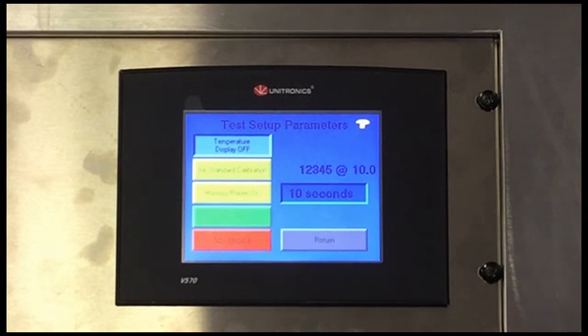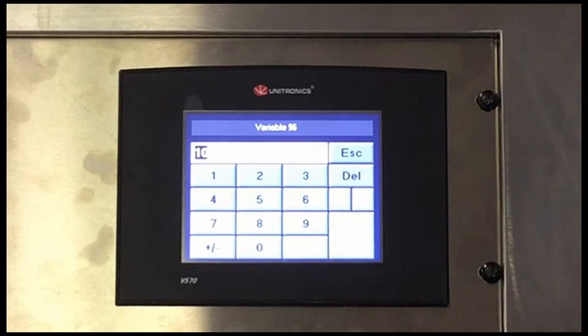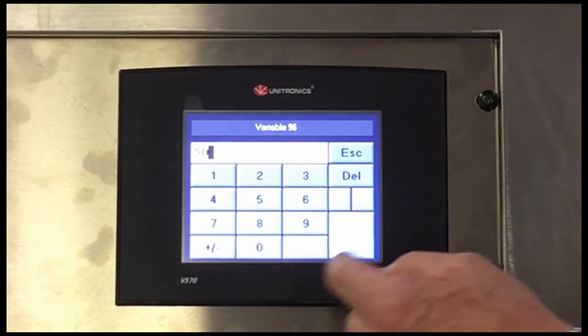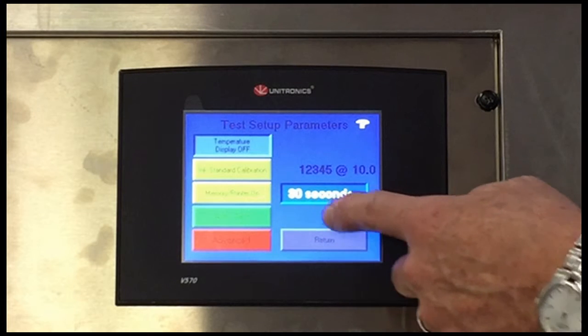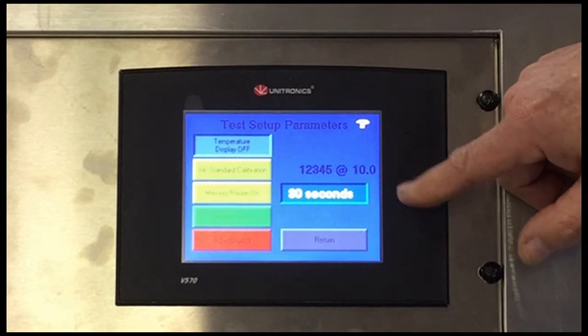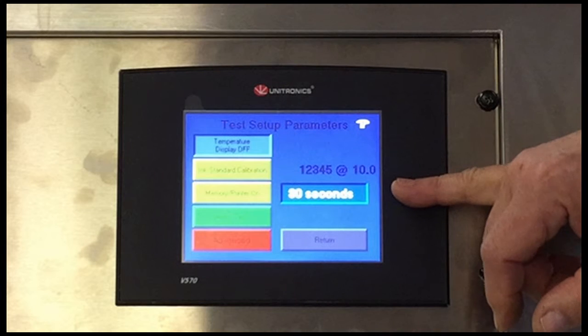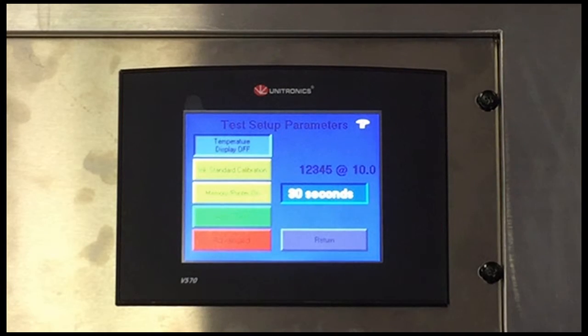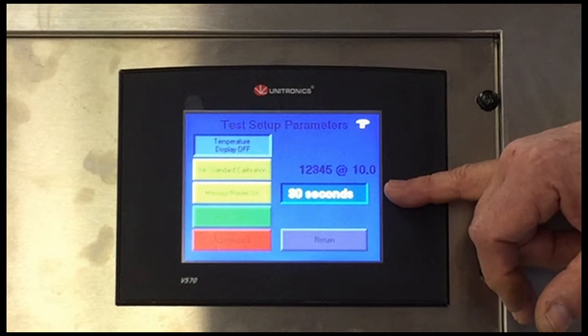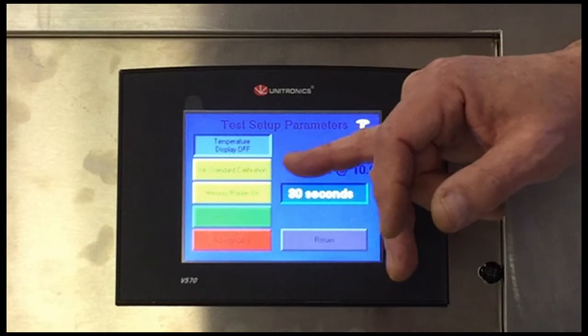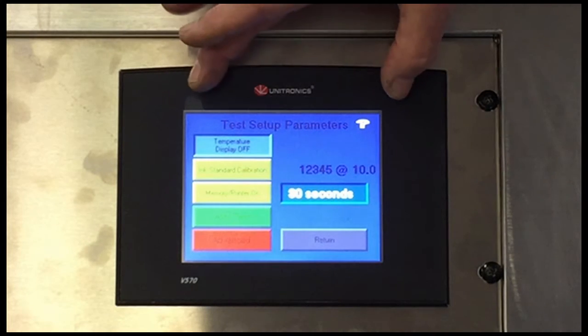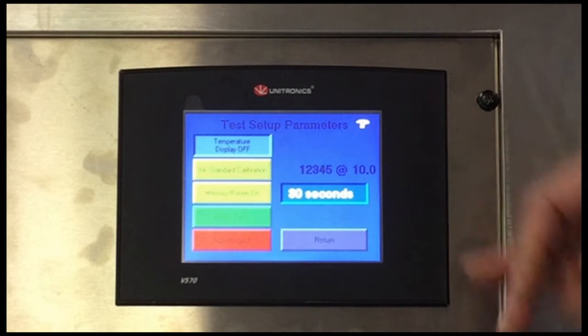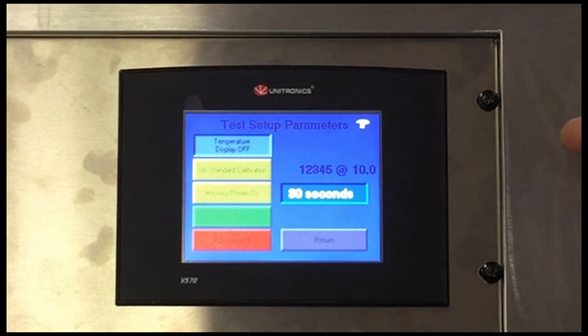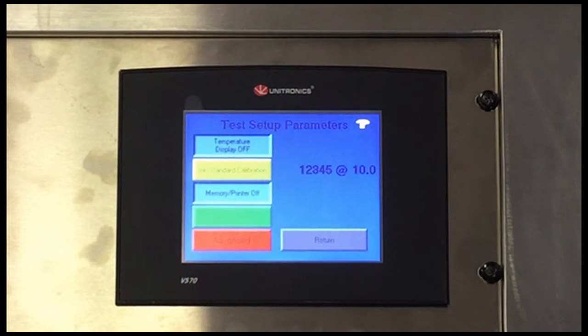If I wanted to have this thing print every 30 seconds, for example, I would just touch this, key in the time interval that I want, and now I've changed my time interval to 30 seconds. So what I've just done is when we run a test, it's only going to print out every 30 seconds instead of every 10 seconds, and also the meter on the panel is going to update every 30 seconds. Now if I want just a live display that's active all the time and I don't worry about the print, then I can simply turn the printer off, and now the printer function goes away altogether.